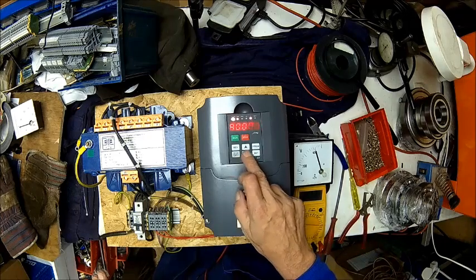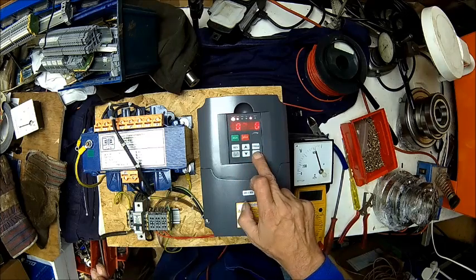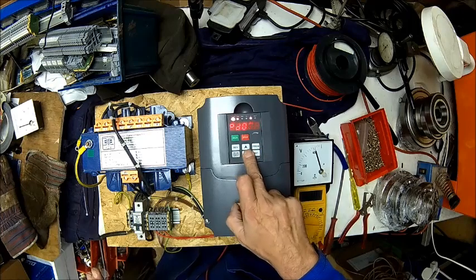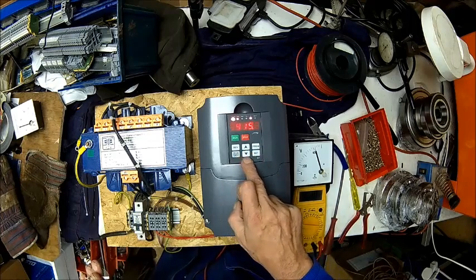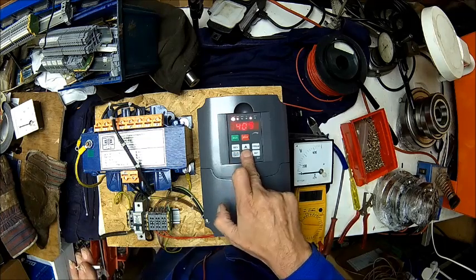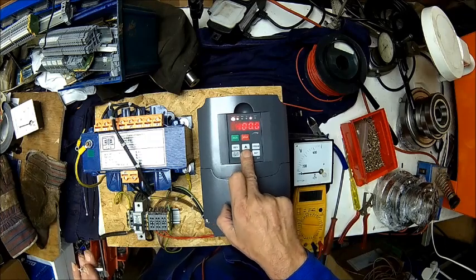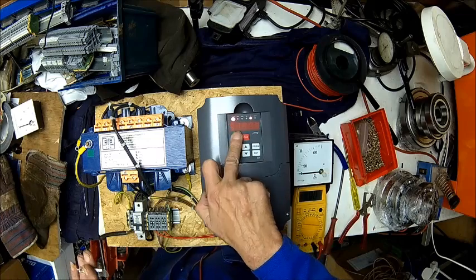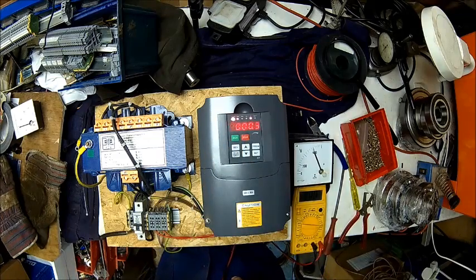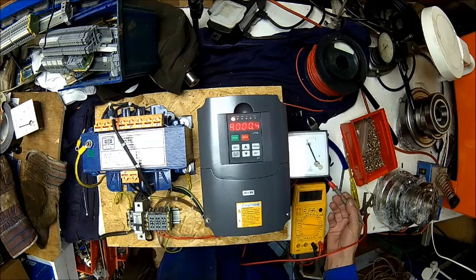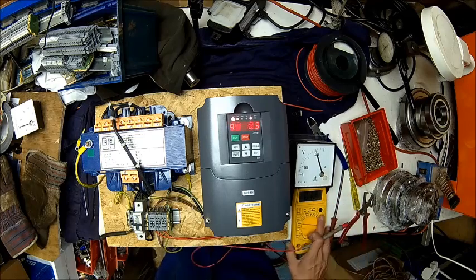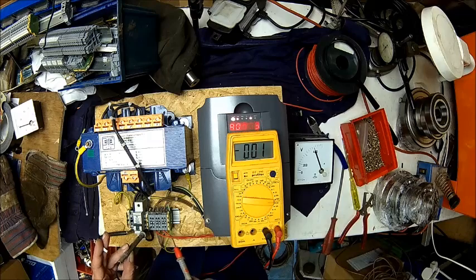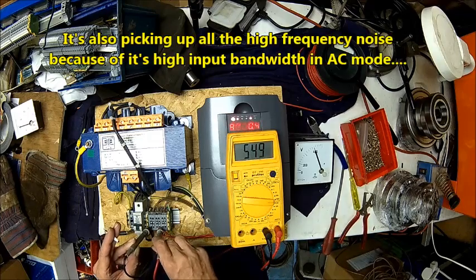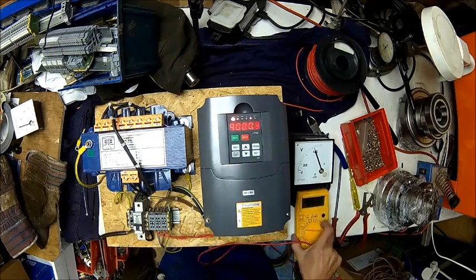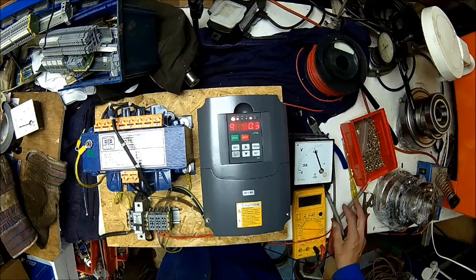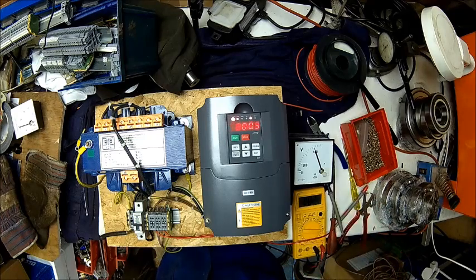So let's say if we change that to, I think it was 8. It was 8. Yeah. Let's change that to 400 so you can see the difference. These are parameters which you cannot change while it's running. So change that to 400, set, run, and as you can see we're reading just about 400 volts, whereas our fancy digital meter reads still 560, 550, which is about our DC voltage. Yeah, so it proves analog technology is sometimes much better than digital technology.